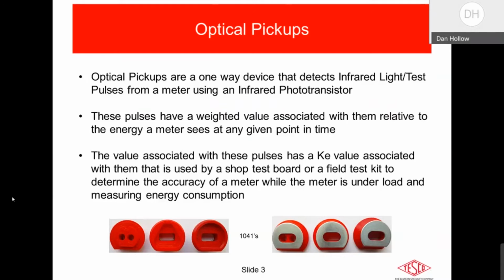So optical pickups are a one-way device. They're just basically the meter putting out an infrared light pulse relative to the energy usage. And that is picked up by a phototransistor in the optical probe or the optical pickup, as it may be. So a pickup is just a one-way device. It's just counting infrared pulses that it sees that are being output by the meter.